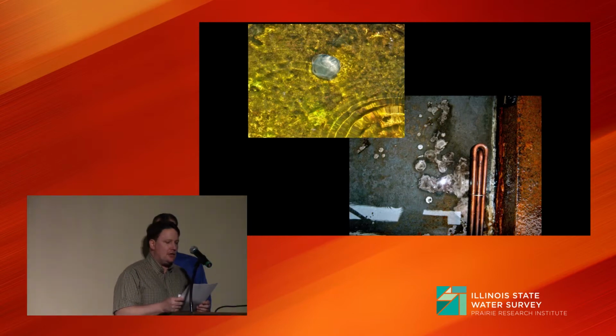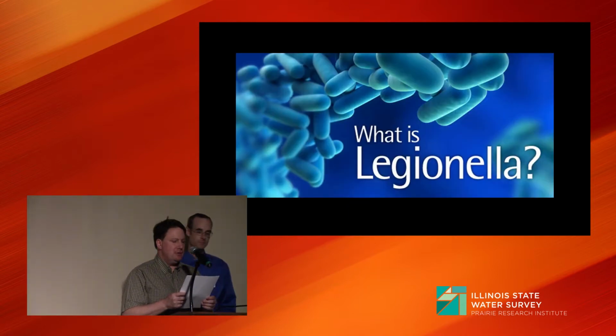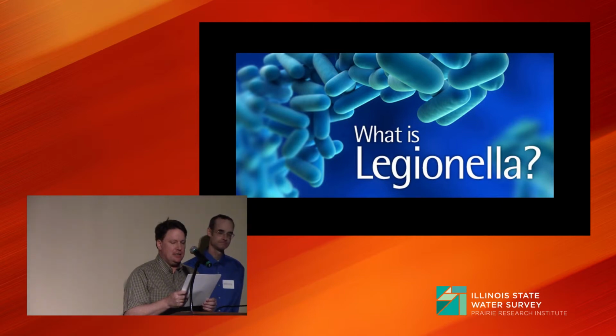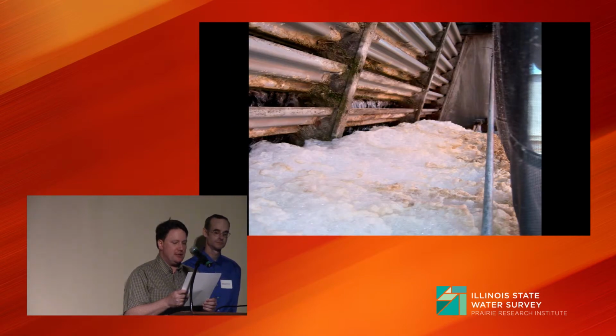Legionella is the bacteria that causes Legionnaire's disease, a severe pneumonia which hospitalizes up to 18,000 people a year with a 5 to 30% fatality rate. Legionella can grow in poorly treated systems of all sorts, but especially cooling towers. Improper water treatment is a public health hazard. Here's a picture of a cooling tower severely contaminated with bacteria and algae being disinfected with chlorine. The foam is the result of the high microbiological kill rate.